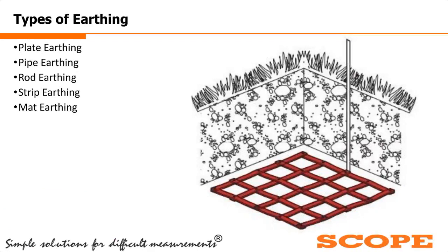Next one is mat earthing. A number of earth strips are connected in a mat form, and all these metal strips are connected to all the earth pits, so that a complete loop is formed. The leakage current flowing through this type of earthing is shared by the different earth pits by using this mat type of earthing.